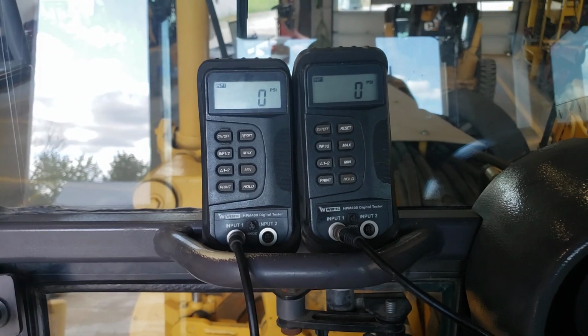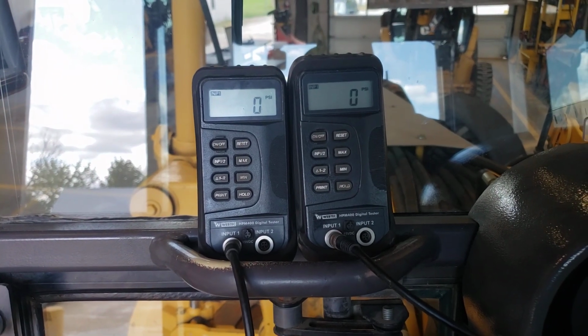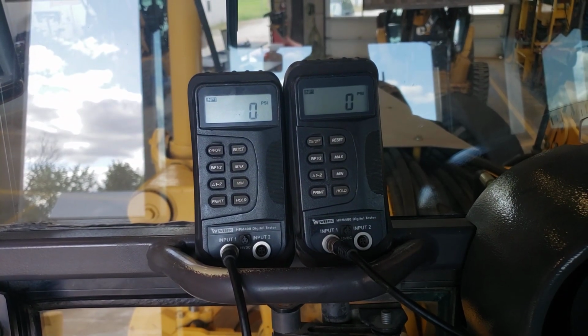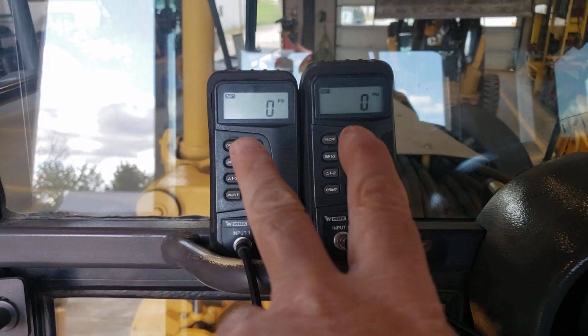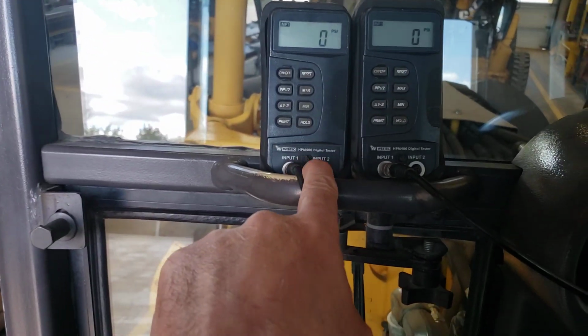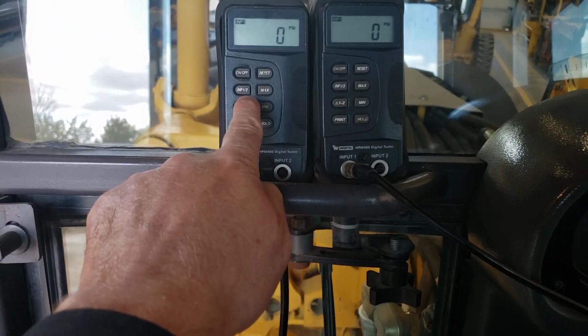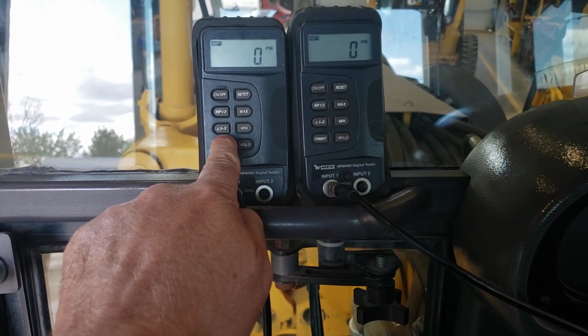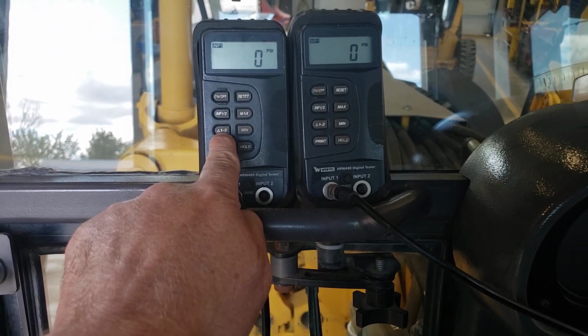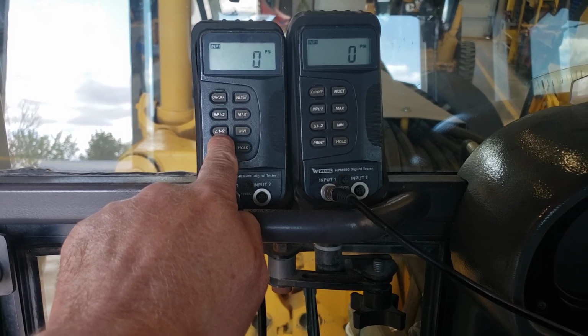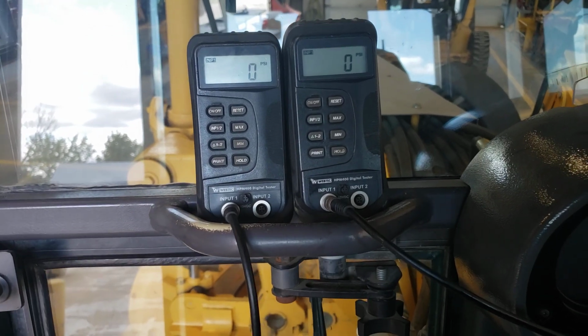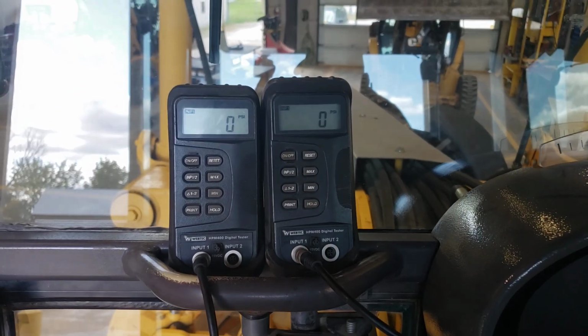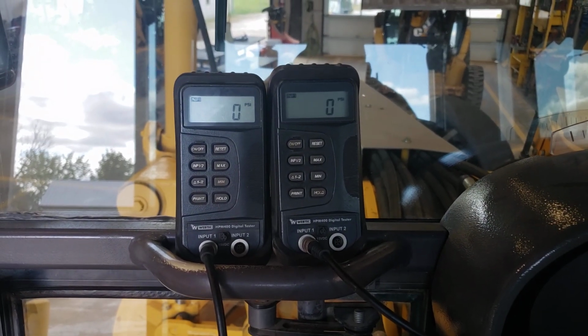I'm not too concerned about the pressures if I'm looking at load sensing. What I'm interested in is the difference, or the delta P. And I don't actually have to use two of these gauges because there's an input 1 and an input 2, and these gauges are designed to work with load sensing systems, so they have a delta 1 minus 2 button. So I can put both readings into one gauge and watch the difference if I don't want to be concerned with the actual values.